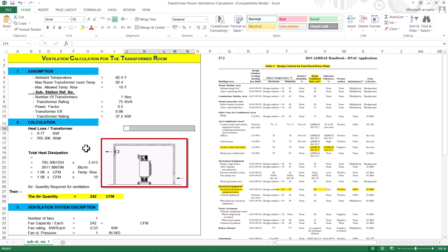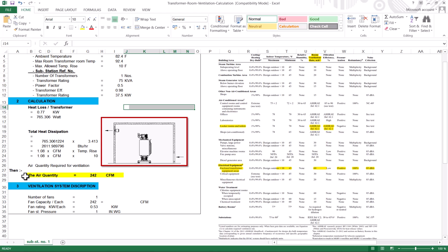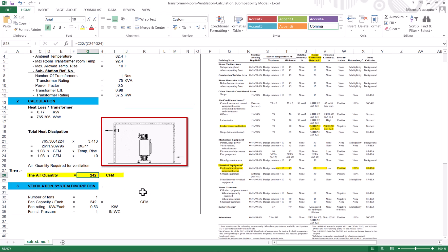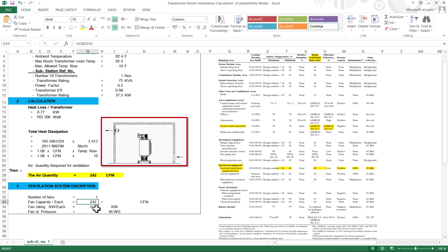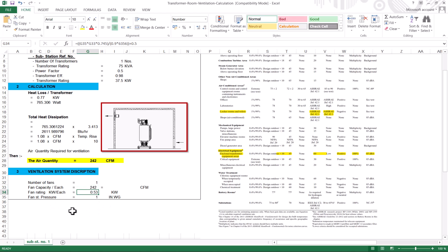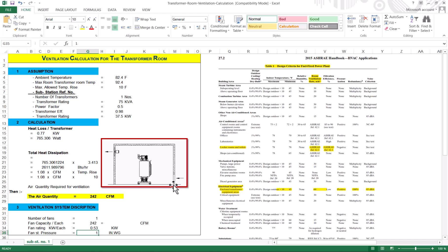You can just put your values into the Excel sheet and get all the results. The required airflow for this transformer room is 242 CFM — we need 242 CFM of fresh air and exhaust to ventilate the room. I am using one fan rated at 242 CFM with 0.5-inch static pressure, though it depends on the ducting and external static pressure requirements. This is the basic calculation for a transformer room. I hope you liked it — if you have any questions, ask in the comments. I will share the files.